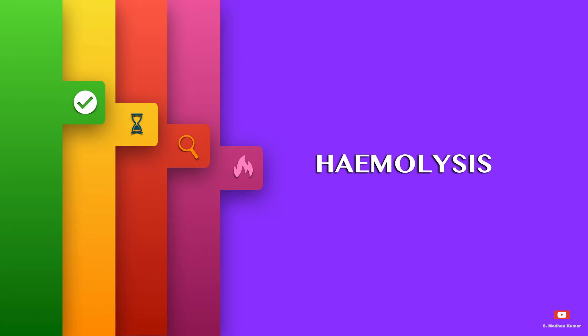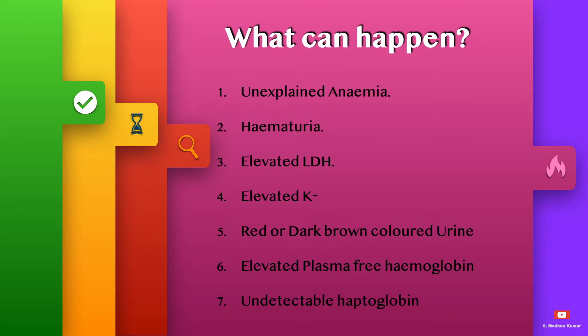Hello everyone. Under the ECMO troubleshooting simplified series, today we will see about hemolysis on ECMO. Hemolysis on ECMO can lead to unexplained anemia, hematuria, elevated LDH, elevated potassium, red or dark brown colored urine, elevated plasma free hemoglobin, and undetectable haptoglobin.